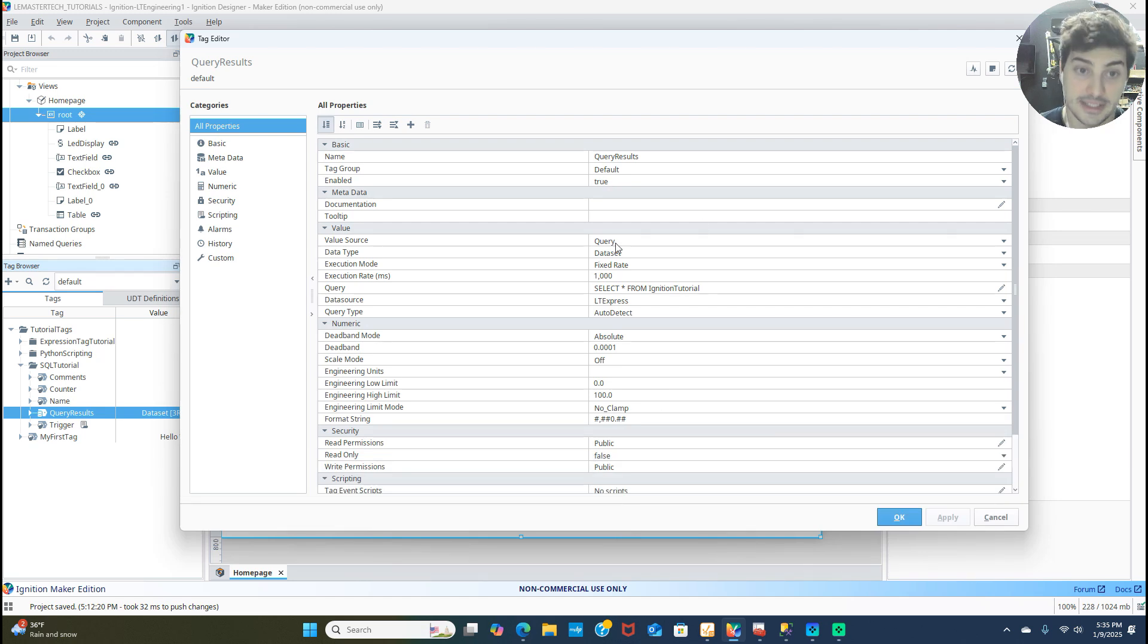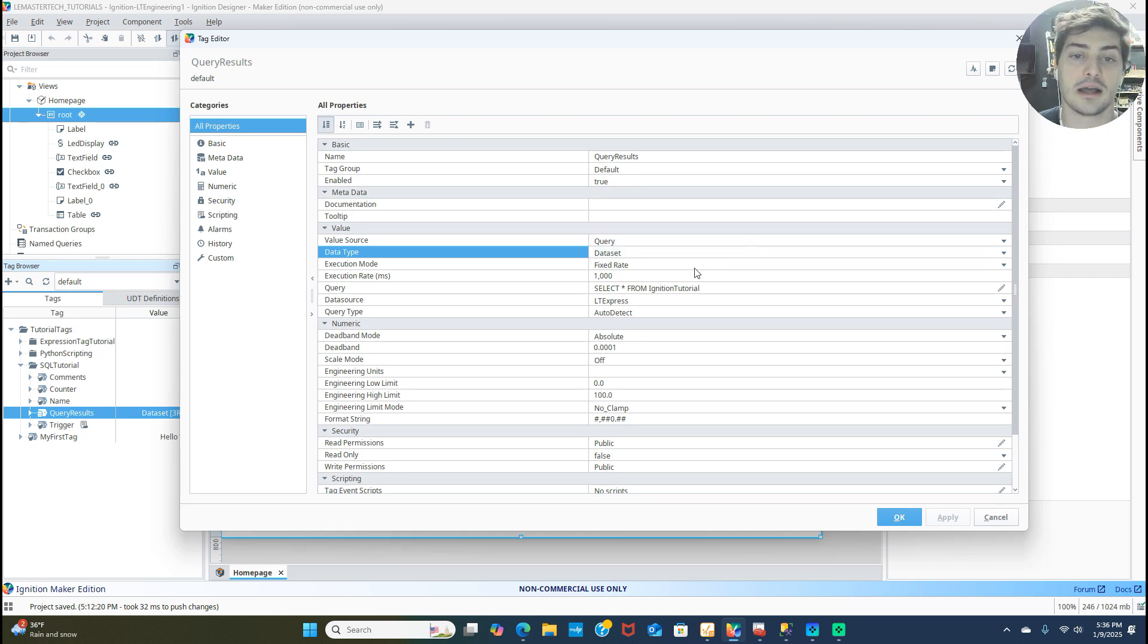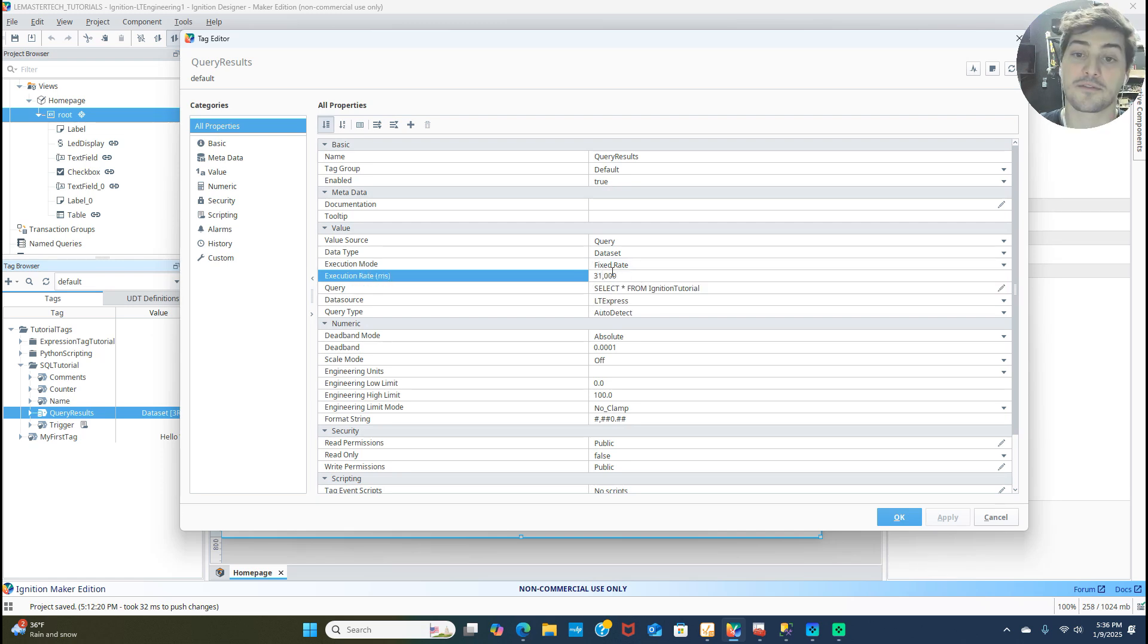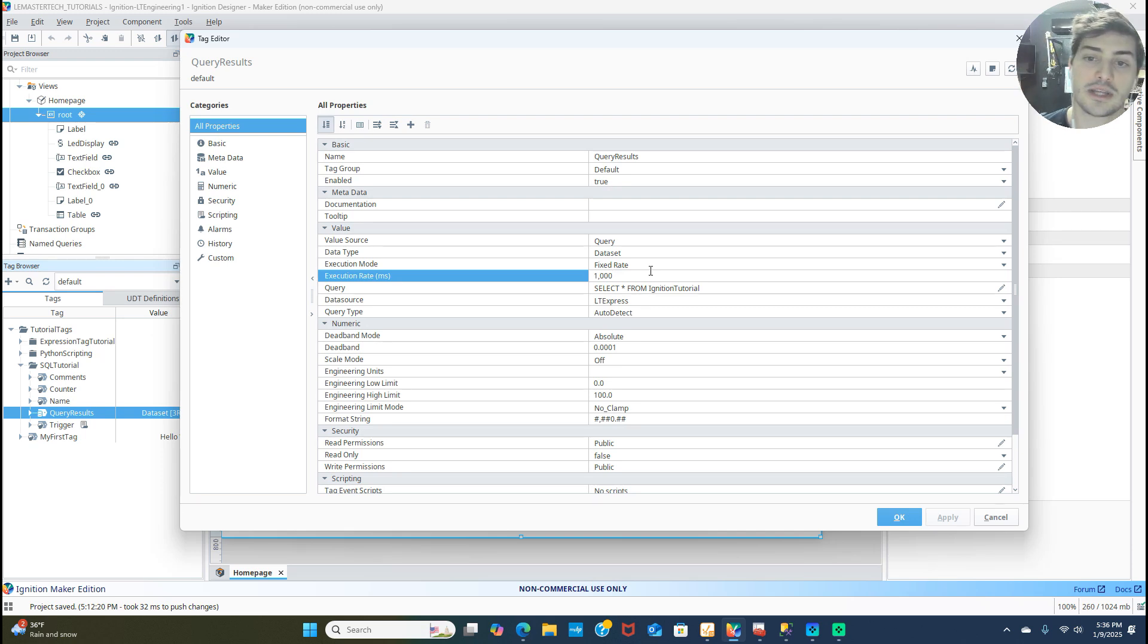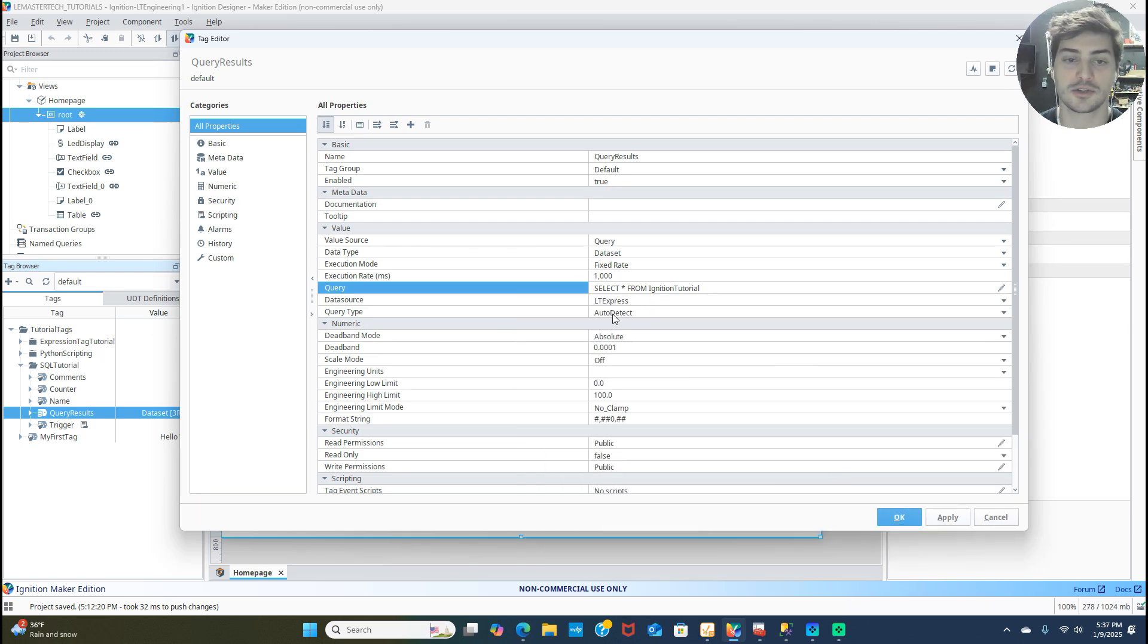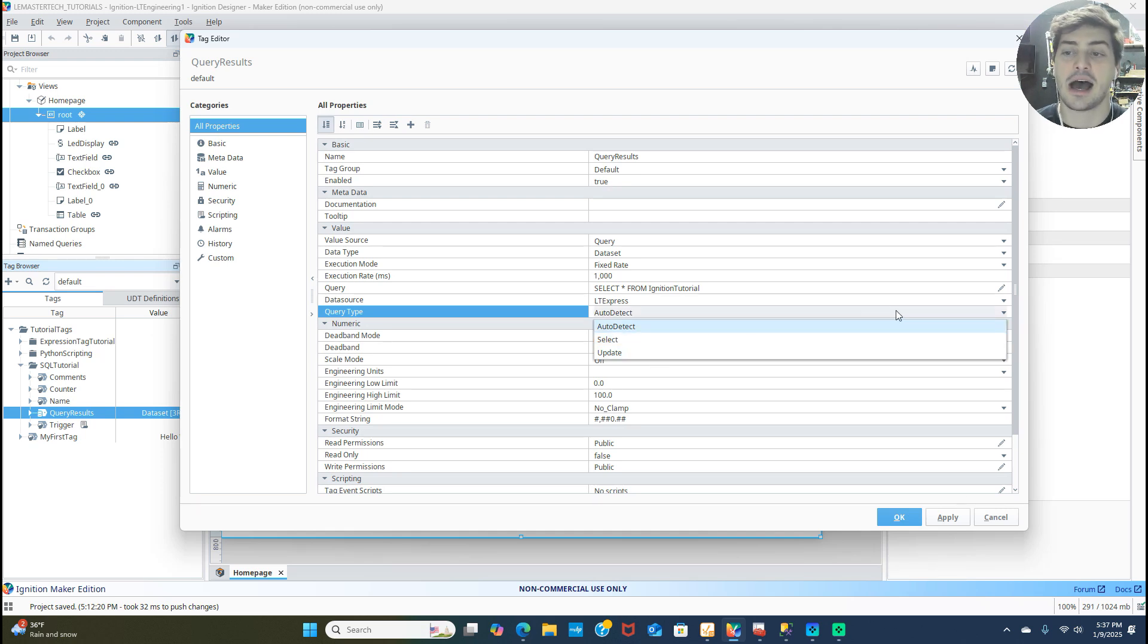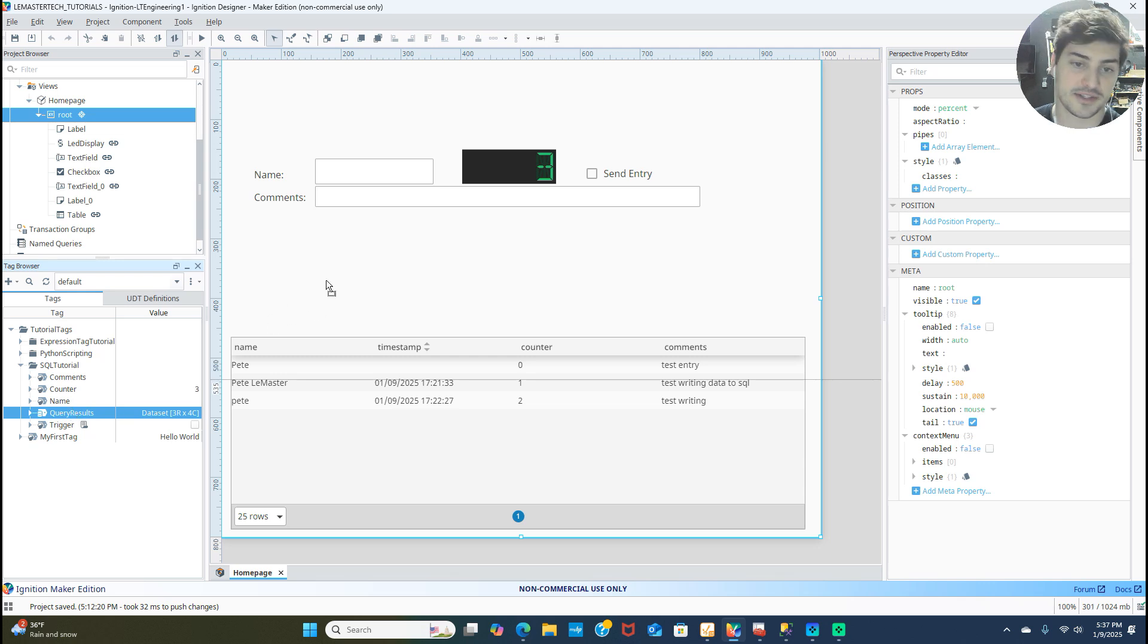So I made a query tag. So the data type is going to be a data set if you're pulling in a whole bunch of results from SQL. If you're just pulling in the max value in a table, this could be an integer or a float or a string or any other form, obviously. Now the execution mode is up to you. Event driven usually means it'll be listening for changes. I like to do fixed rate for execution rates because I can slow down less important things. But for this, it's just a quick little list of names and comments. So I'm going to check for changes every second. And that'll look good on the HMI as well when we're entering new data. And I'm going to use that same query, select all from Ignition tutorial, select everything from Ignition tutorial. It will pull in data every one second. You tell it what data set to use again, just like in that database query tool. And you can tell it specifically if it's a select or an update, but I'm just going to let it auto detect.